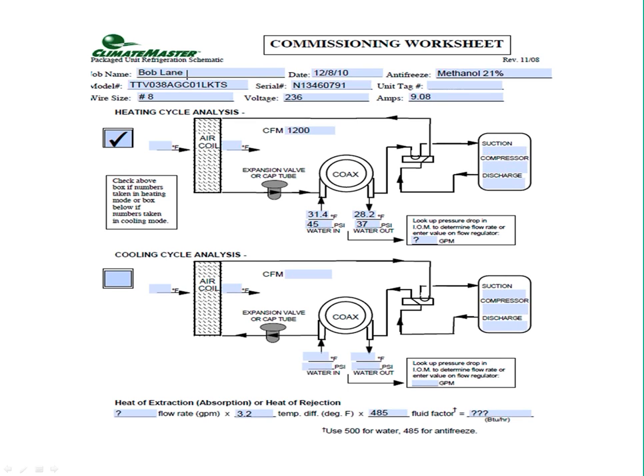Our pressure difference, so we have 45 psi entering and 37 exiting. Well, I can tell you that that large pressure difference is pretty much off the charts for our flow rate. If I was to extrapolate or interpolate, probably 11.5 or so GPM. Well, I'm not going to tell you should go ahead and interpolate, because you're going to be off the charts anyway by calculating this heat of extraction.